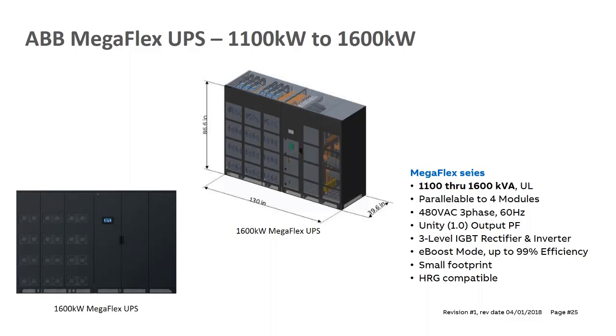And then the biggest member of the family on the monolithic side, also what's called a block UPS, a single block UPS, is the MegaFlex, which is available from 1100 kW up to 1600 kW or 1.6 megawatt building blocks. All of them are parallelable, to get to more power or redundancy. And as you look at the main features on the right of the slides here, they're very similar. They can do the same thing. It's just more power. One unique feature, and actually two things I'll point out with the MegaFlex, is that it can handle high resistance grounding. We don't see that a lot in data centers. It's more often seen in industrial applications, but once in a while we do come across it. So the smaller model cannot handle that, but the MegaFlex can. It's designed as standard to operate in a high resistance grounding environment.